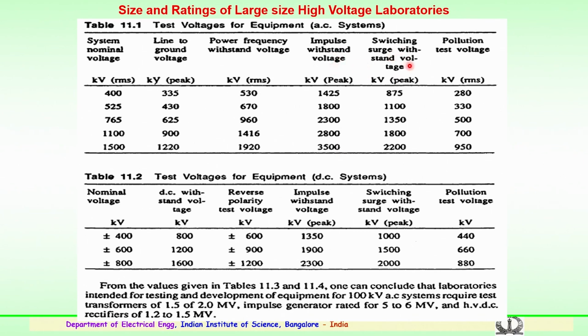For switching surge voltages it is 250 by 2500 microseconds, where for a 400 kV system the switching surge withstand level could be 875 kV, where the equipment should be able to withstand these surges for a specified number. It could be 10 positive and 10 negative applications, or 5 positive and 5 negative applications. These are normally specified in the standards and an agreement between the manufacturer and the utilities. Similarly, for 765 kV you have to see that the switching surge withstand voltage is 1350, and for the higher voltage 1100 it is 1800 kV and so on.